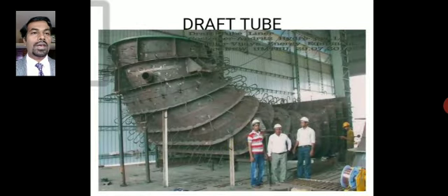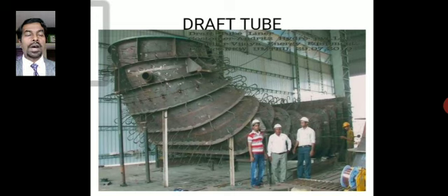This is the last piece of the power plant which we see here. It is a draft tube. A draft tube is a tube whose area gradually increases, and finally through the draft tube the water comes out of the power plant. Some of the turbines like the Francis turbine and Kaplan wheel normally have a very low exit pressure. So with very low exit pressure, it will be very difficult for the water to come out of the turbine into the atmosphere, where the atmospheric pressure will be more than the exit pressure. So in order to avoid that, we have a draft tube.